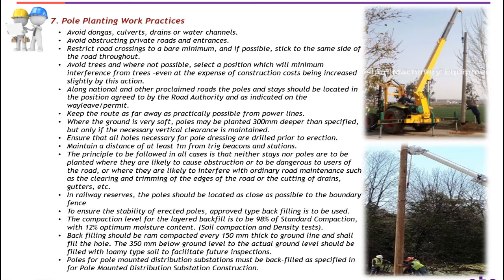Number eleven: in railway reserves, poles should be located as close as possible to the boundary fence. Number twelve: to ensure the stability of erected poles, an approved type of backfilling is to be used. The compaction level for the layered backfill is to be 98% of standard compaction with 12% optimum moisture content while performing compaction and density tests.